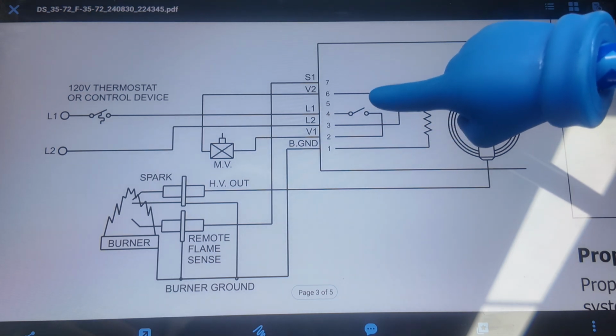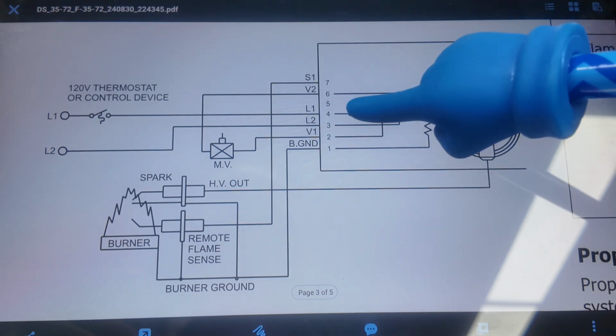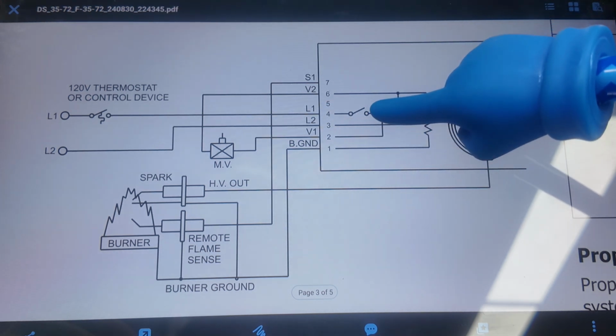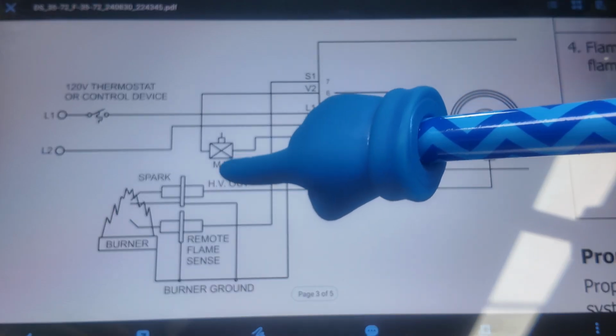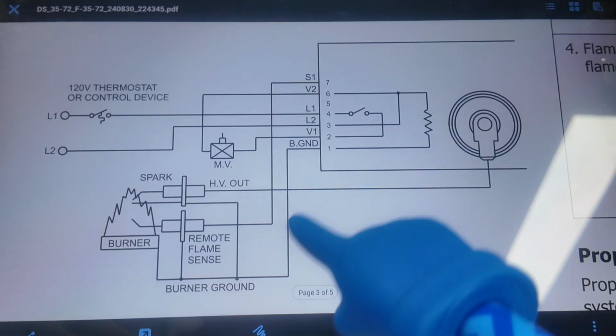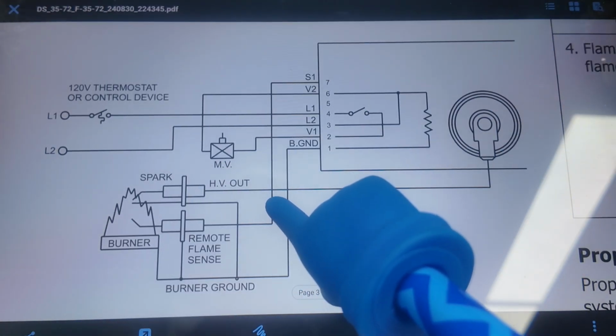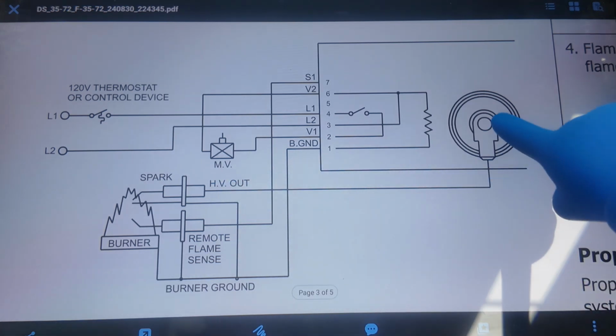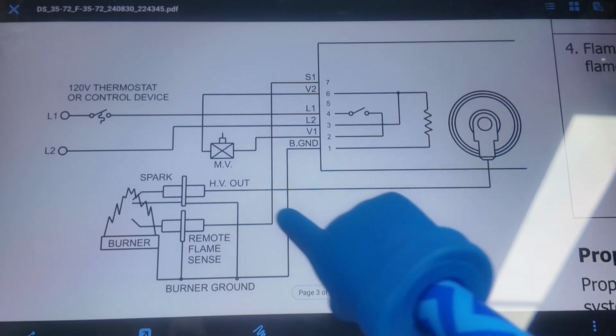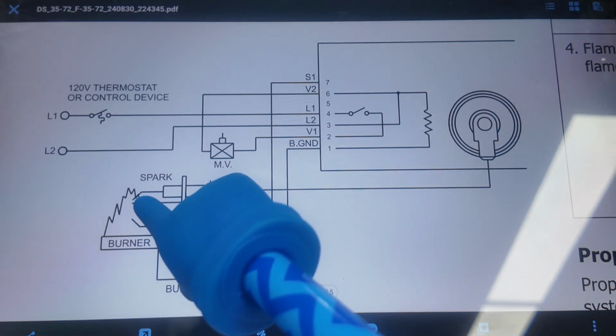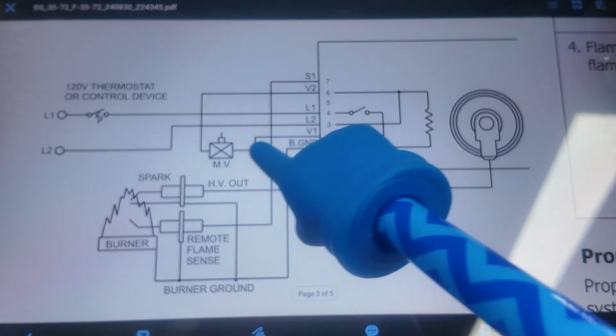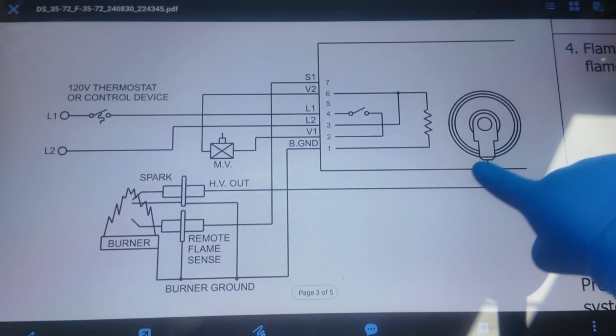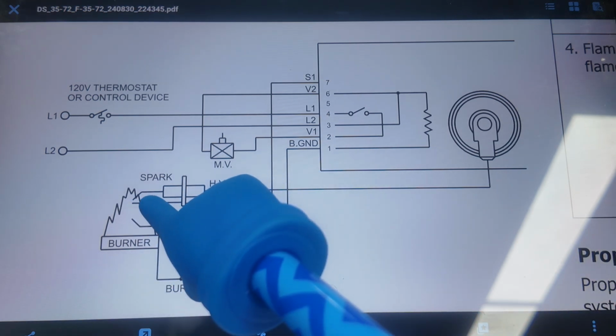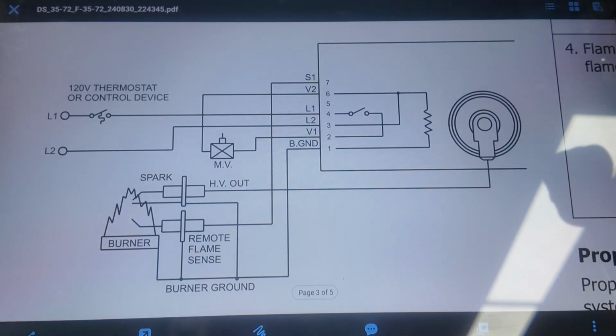So after 4 seconds, this switch closes. It puts electric out to the main gas valve. And it puts high voltage out the ignition transformer to arc off the ground. So this is going to spark to make it light. V1 turns the gas on. Our high voltage makes the spark to make the burner light.